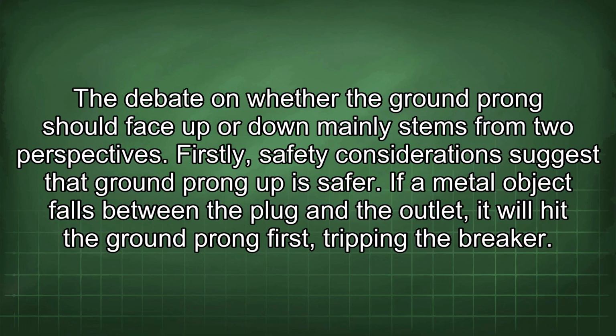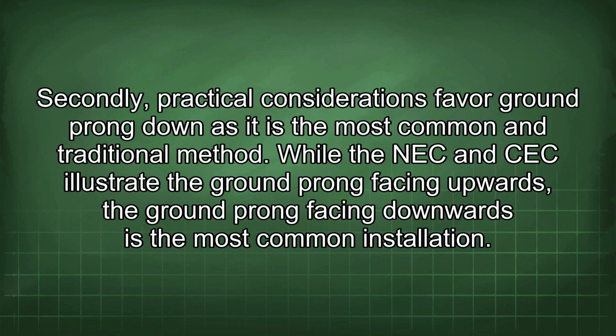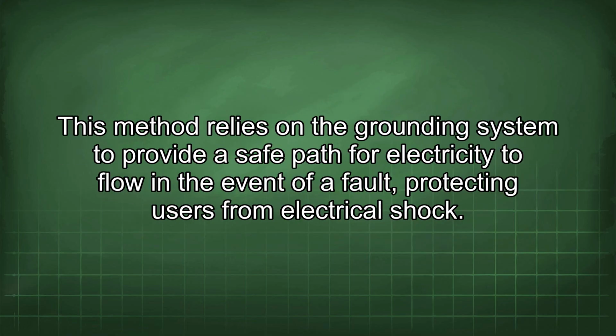The debate on whether the ground prong should face up or down mainly stems from two perspectives. Firstly, safety considerations suggest that ground prong up is safer. If a metal object falls between the plug and the outlet, it will hit the ground prong first, tripping the breaker. Secondly, practical considerations favor ground prong down as it is the most common and traditional method. While the NEC and CEC illustrate the ground prong facing upwards, the ground prong facing downwards is the most common installation. This method relies on the grounding system to provide a safe path for electricity to flow in the event of a fault, protecting users from electrical shock.